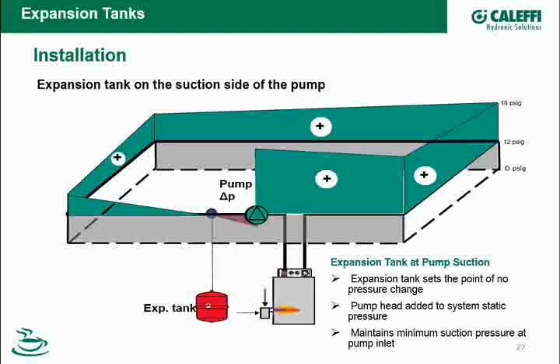The pump, based on its pump curve, will generate a certain amount of differential pressure and flow rate depending on the losses through the system. Now, it doesn't increase pressure or decrease pressure. It generates a delta P, or differential pressure, and that's tied to its point of no pressure change. So I put the expansion tank on the suction side of the pump. In this drawing, for instance, this is 12 psi here. That's my static pressure, my minimum pressure on the system. Now, with the expansion tank on the suction side, the pump's head pressure, or its delta P, is additive above the static pressure of the system.